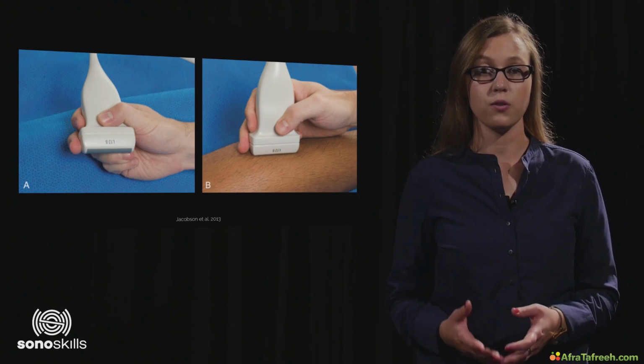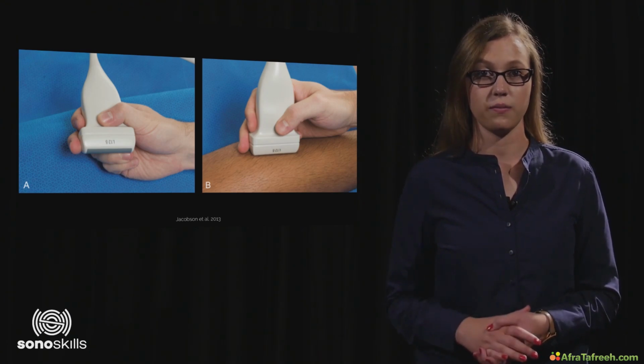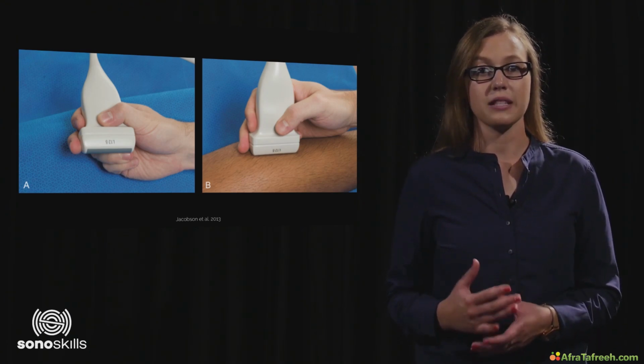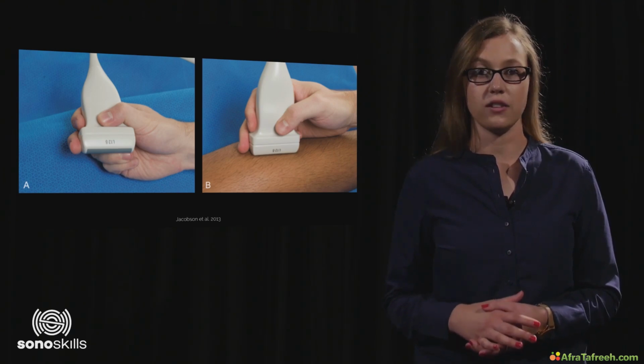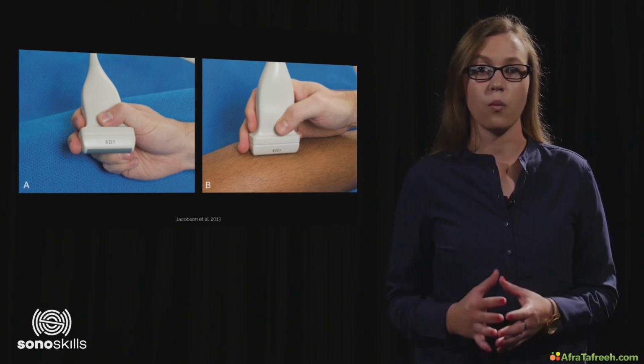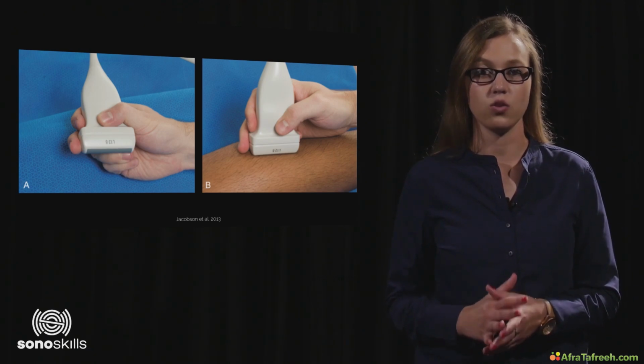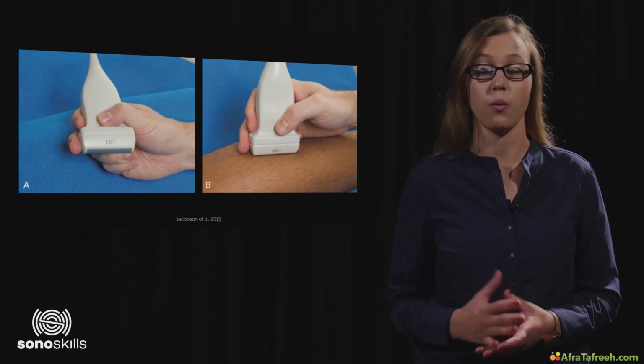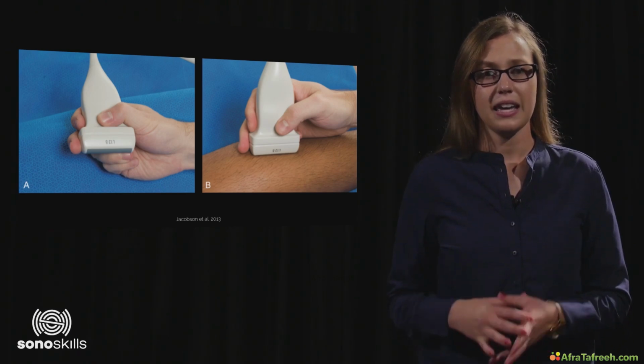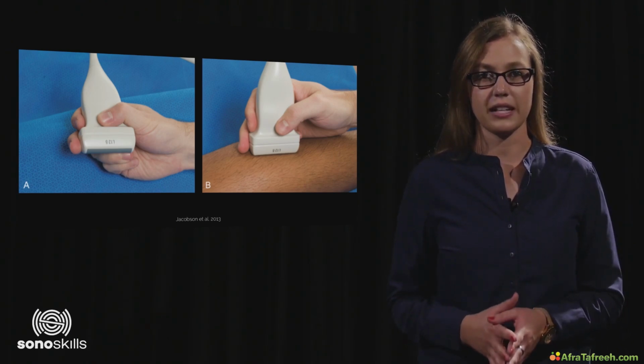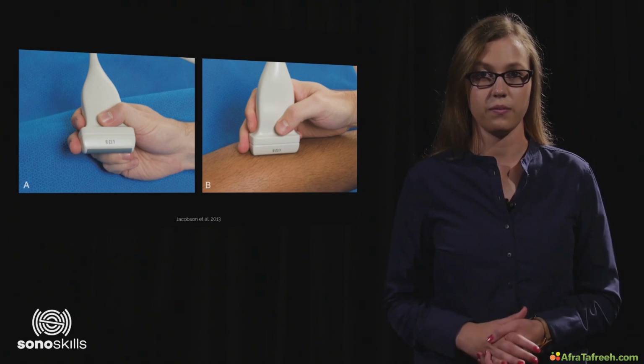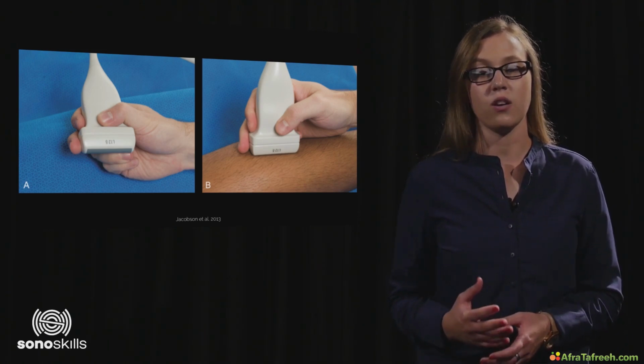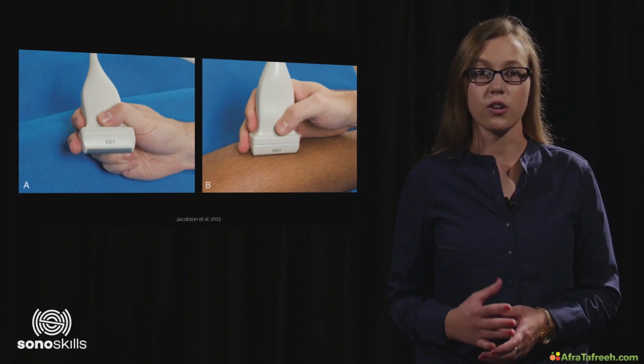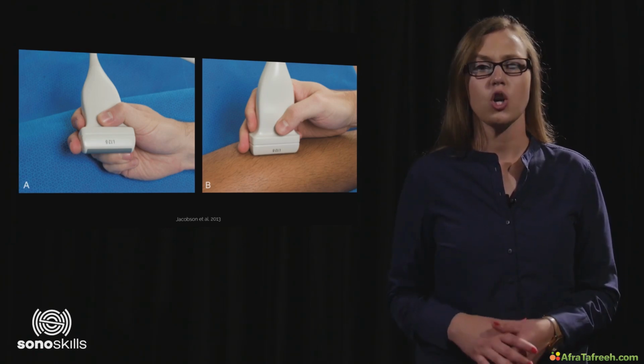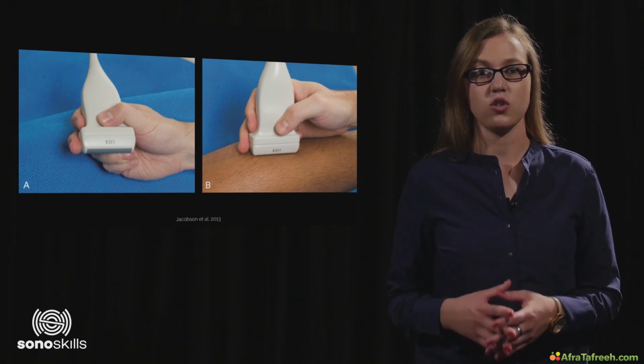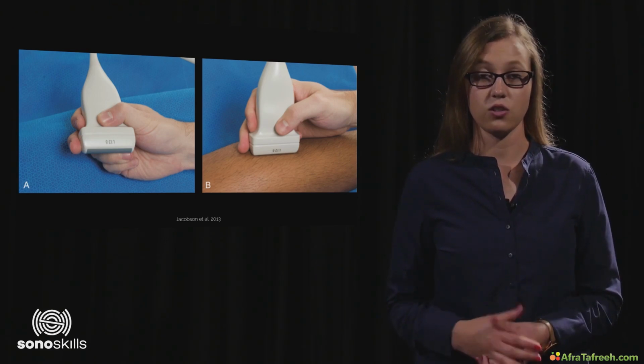First of all, it improves the stability of the transducer. It prevents it from sliding away due to the ultrasound gel and ensures that one maintains a steady and controlled course of the transducer while scanning. The second reason is that the skin contact provides tactile input. The fingers that rest on the patient's skin feel the curves and shapes of the patient, which gives you the chance to adapt the transducer angulation to any changes.